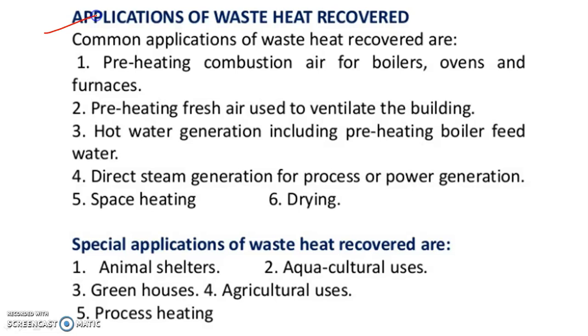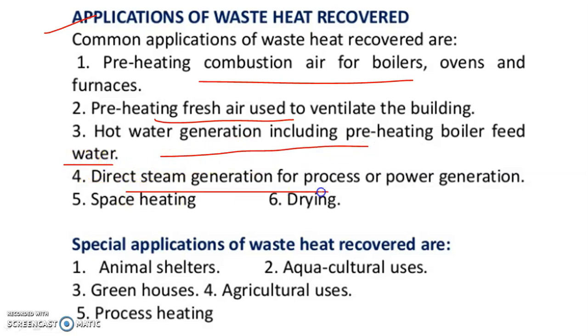These are the applications of waste heat recovered: preheating combustion air for boilers, ovens and furnaces; preheating fresh air used to ventilate the building; hot water generation including preheating boiler feed water; direct steam generation for process or power generation; space heating and drying. Special applications of waste heat are animal shelters, aquacultural uses, greenhouses, agricultural uses and process heating.